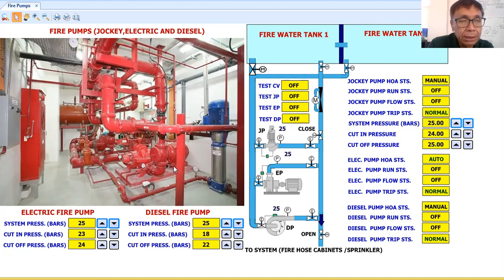So each pump, the company that will deliver the fire pumps, it will be coming in a set, okay? So the jockey pump will come with a motor control. Then likewise, electric and diesel will come with a motor control panel equipped with a controller, or a PLC. Then in electric and diesel, their control panel will be equipped also with a pressure sensor, okay? Now, first, this jockey pump, the control for this is a pressure switch, okay? So, jockey pump, electric pump, and this diesel pump. For the diesel, it will be driven by a diesel engine. Now, for the electric, of course, it will be driven by electric.